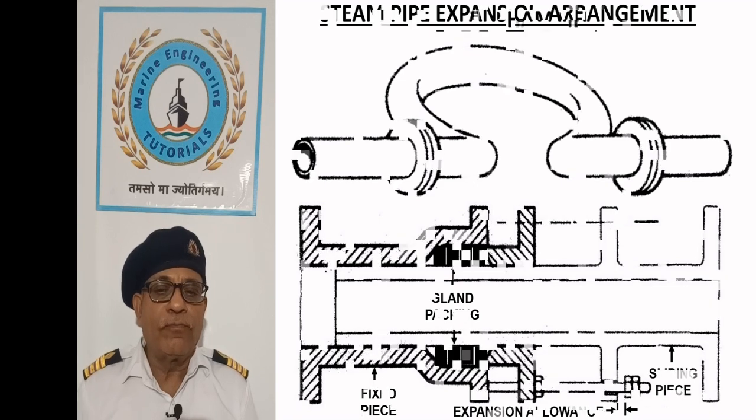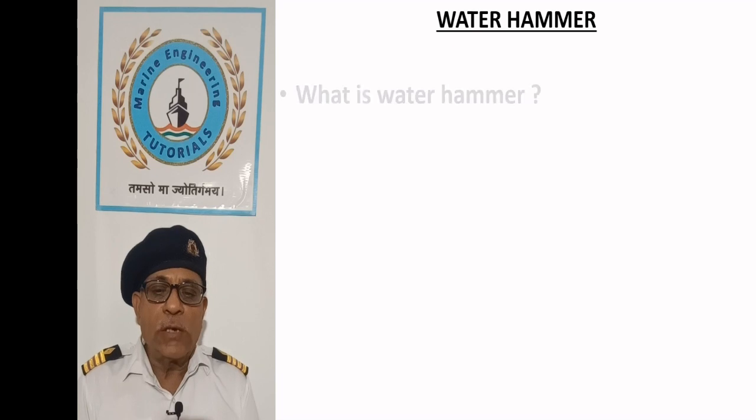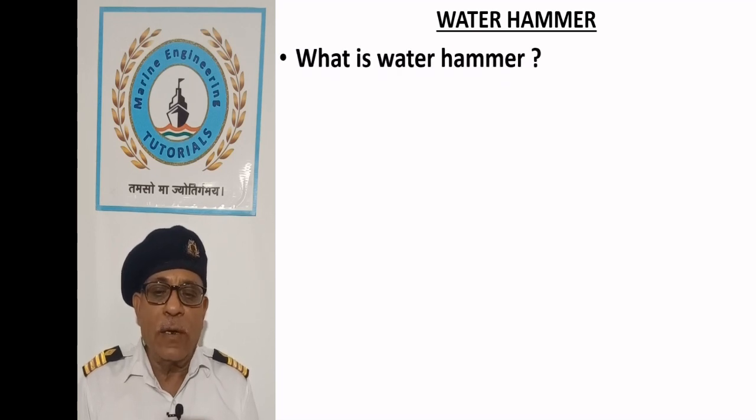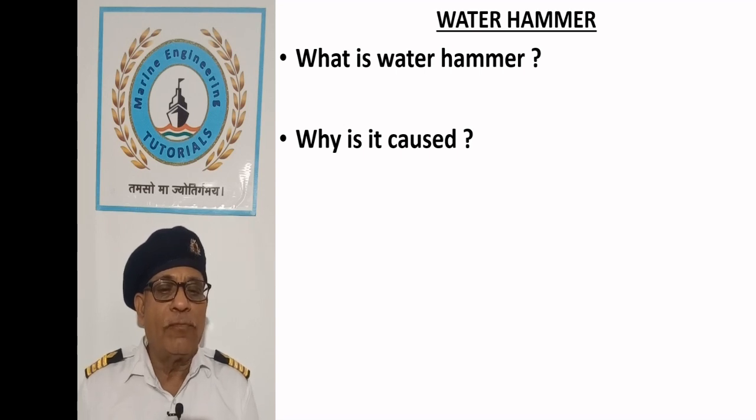Water hammer. What is water hammer? A severe and repeated banging in steam pipes is called water hammer. Why is it caused? Water hammer is caused when steam is admitted to pipes containing water, especially when the pipe has a slight inclination from the horizontal, which allows the water to have a large free surface area.